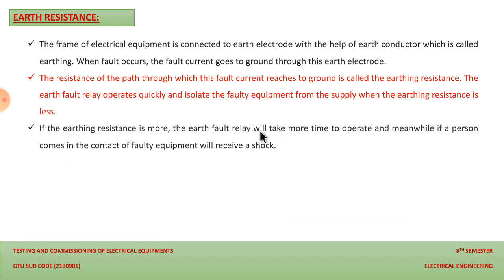And if earthing resistance is more, then the earth fault relay will take more time. It means the low current will transfer through that heavy resistance, and because of that the relay will not get sufficient current to get energized. So yes, it will take more time to operate. And meanwhile, if a person comes in contact with the faulty equipment, they will receive a shock, or the instrument which has that high discharge of current will become faulty. So this is the main point that we should keep in mind.